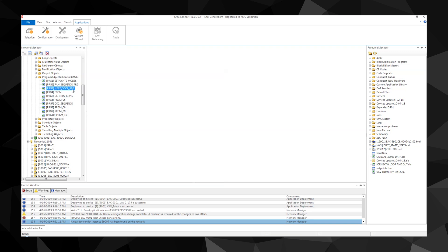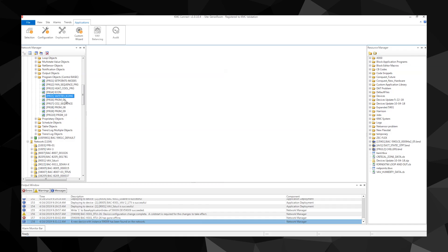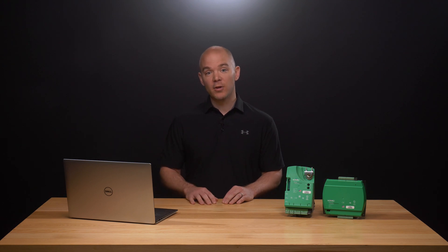This then happens again for the heat cool and economizer control programs. Finally, the last program is safeties and interlocks. As the last program in the sequence, any logic that would preclude outputs from turning on at the same time or off too soon — which may damage the equipment — should be located here. This allows any overrides to previous logic to be made prior to the scan ending and the outputs being updated with their new values.